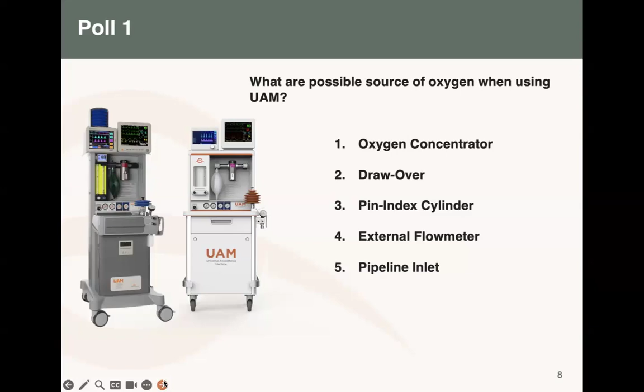Actually, with the UAM you can use five sources of oxygen. As I said before, the main source of oxygen is the concentrator, and that should be your main source of oxygen when using this machine. Of course, there's a draw-over where you can draw in air, and remember that provides you with only 21%. But there's also the option for cylinders, the pin index ones, and also the option for pipeline. And most of you, I understand, don't have the plant, so you don't have the pipeline. So when we are using the big cylinders, this is where we always connect.